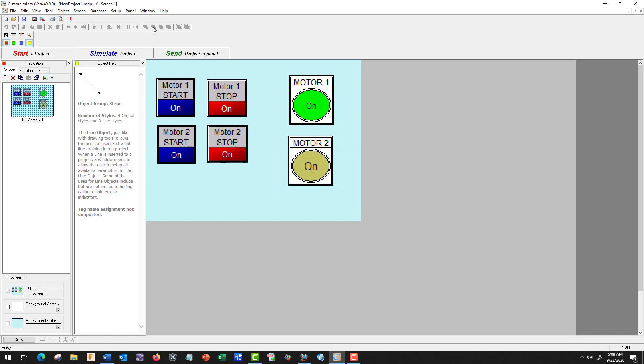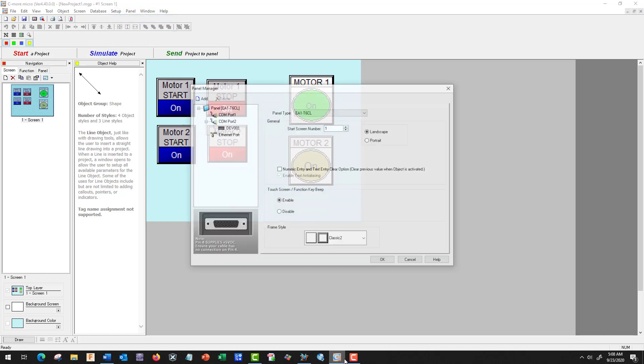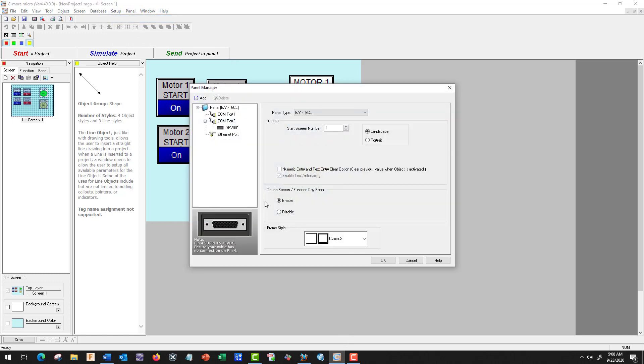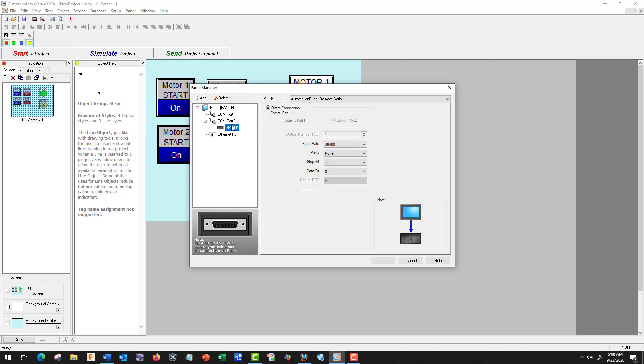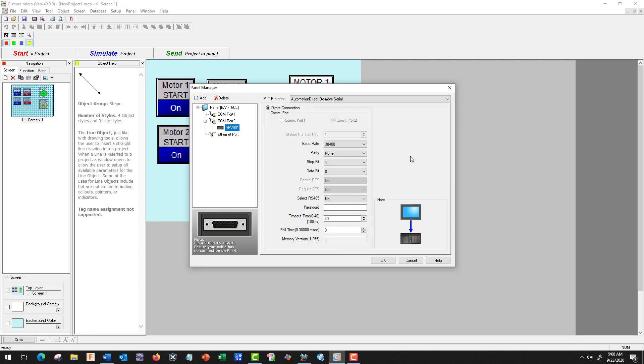Let's go to Setup, Panel Manager. We should have our EA1T6CL. We're going to go here to our COM port, and we should have 38,400. They should all say the same. This is the default for this screen, so we just need to make sure that both our PLC and this one are set for 38,400 in order for them to communicate.